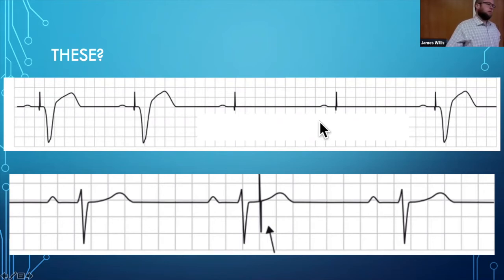So there are two types of failure to capture. There's genuine failure to capture the pace, where there's an issue with energy. It's mainly that the output is too low, or your lead is broken or misplaced. So there's something wrong with the device itself. It's unfortunate when that happens because you kind of start all over again. And then there's also something called functional noncapture, where the energy is delivered, but it's delivered during a refractory period, so it's not really going to do much for you because the heart is not at a time when it's ready to contract again.